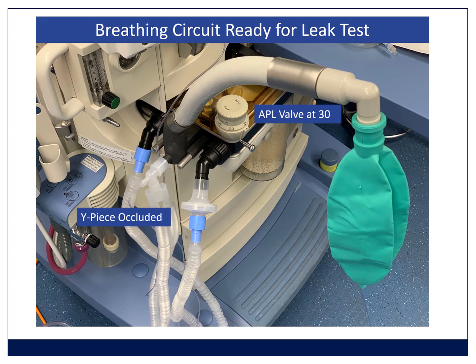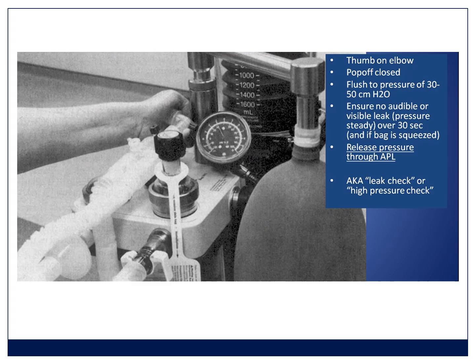Here is another way of doing it. So the Y-piece is occluded. You can see it's plugged in. This is a Drager machine. The APL valve is set to 30 in this case. And you can run your leak test like we told you, but actually these machines will do it for you. So you say, I'm going to run a leak test. It then fills the circuit with air until there's a pressure of 30. And then it works out how much air it needs to put into the machine to keep the pressure at 30. Depending on how much flow is needed, that's how much the leak is. So that's the other way of doing this.